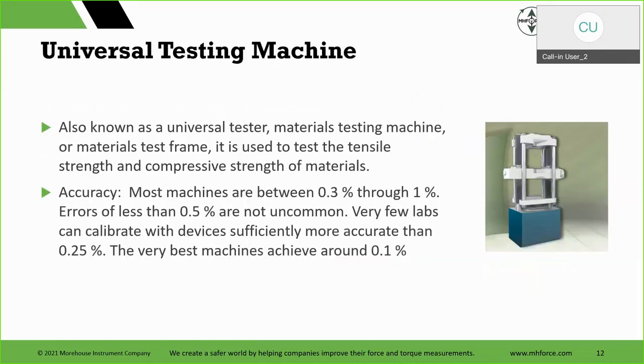So universal testing machine, also known as a universal tester. These are materials testing machines, test frames. Some people use these for force measurements. It depends on what you want to do for accuracy. They're very rigid. That's good for them. But most machines are between 0.3 and 1%. Errors of less than 0.5% are not uncommon. Very few labs can calibrate the devices more accurately than 0.25%.